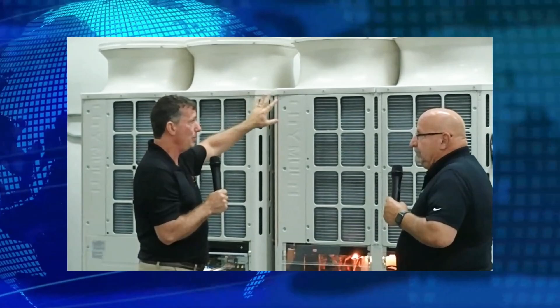So as a service technician I love this idea, because if I had both of my condenser motors feeding into one common board and I had a board failure or a motor failure, I could lose everything. But now, if something happened to a motor or to a board, I could actually isolate a system, and now I have a full variable speed motor, so I can still modulate capacity off one motor. A lot of times when we think about redundant systems, we'd have one that was single speed and then a variable speed to compensate for it. You're actually using two completely independent variable speed controls for the two condenser motors on this unit. That is correct.